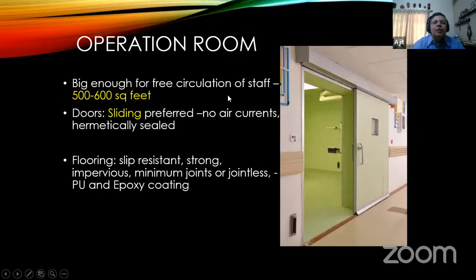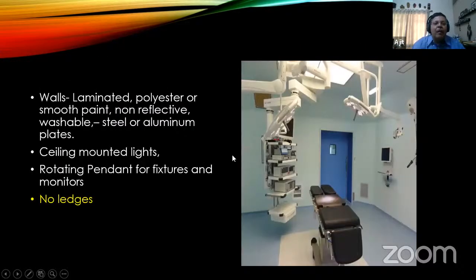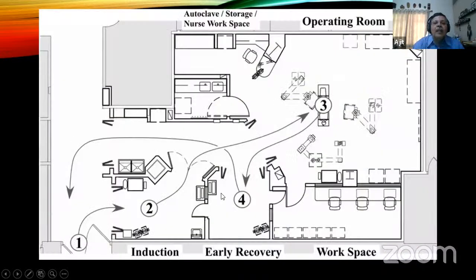The operation theatre should ideally be 500 to 600 square feet, so you can comfortably move around the operation table without changing its position for each surgery. Sliding doors are preferred, and the floor should be slip resistant. We've already seen the walls and ceiling mounted lights. There should be no ledges inside the operation theatre, since ledges are places where dust can accumulate.